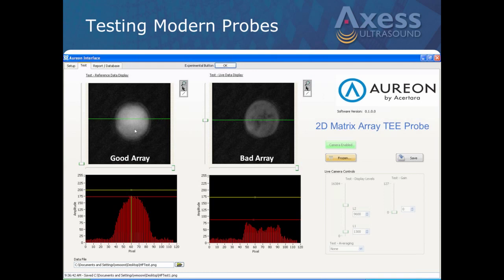And I'm going to show you an image on this device. This is a great example. This is a transesophageal probe, a 2D transesophageal probe. What the Aureon does a really nice job of is helping you identify whether you're getting any kind of acoustic power to the array. In other words, is the array working? If you look here on the left, here's a picture showing a nice bright array. This is a good array, so you can tell even from here that they're getting full electrical and acoustic power to the array. And through this beam profile, you can see that it is firing properly and all elements are working.